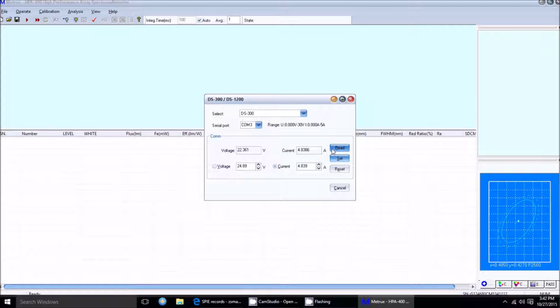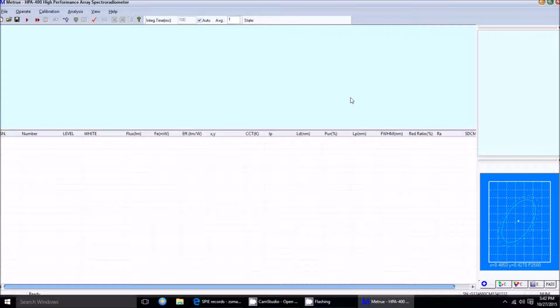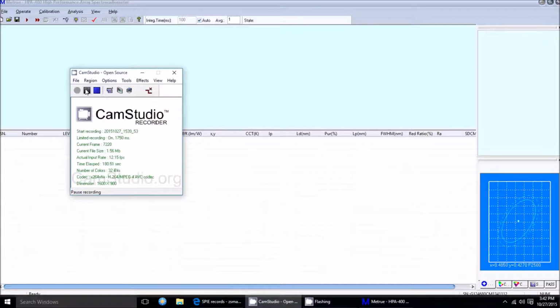Okay, so the lamp is turned on. Typically it takes about 30 minutes for it to warm up such that it outputs light at the calibrated level. So we will have to now wait for it to warm up. So we'll just wait for 30 minutes, and I'll be back in 30 minutes. Close this, it doesn't affect the power supply at all. Alright, so it has been just over 30 minutes since I turned the lamp on. Over is fine. Under, you shouldn't go under.